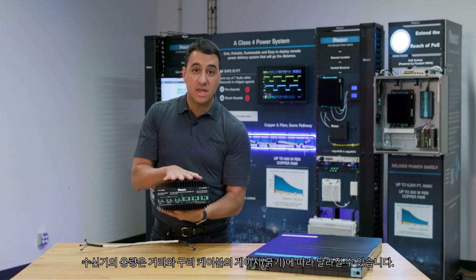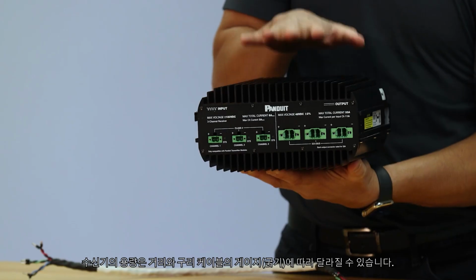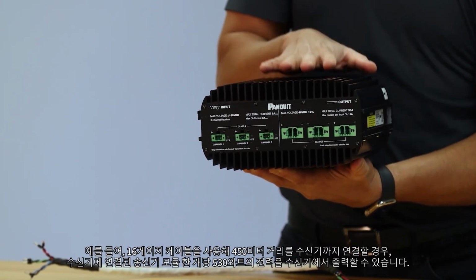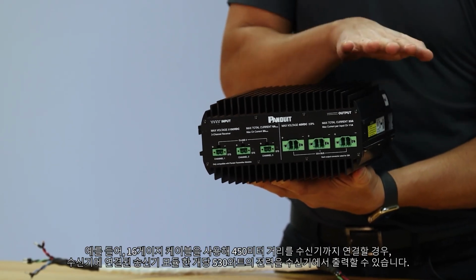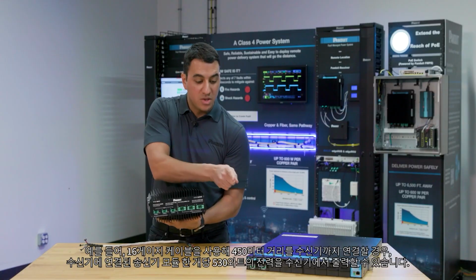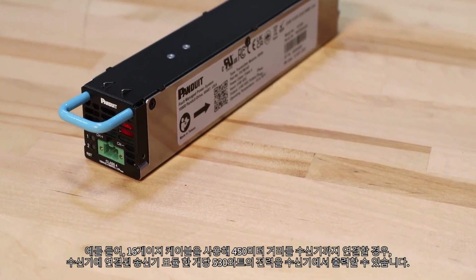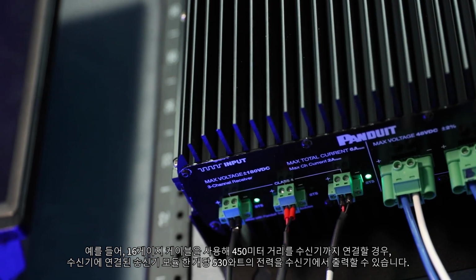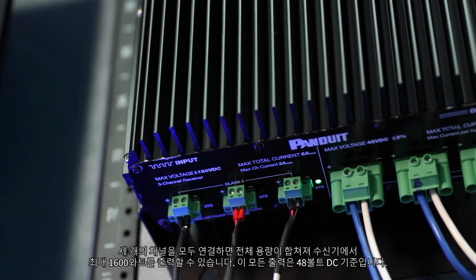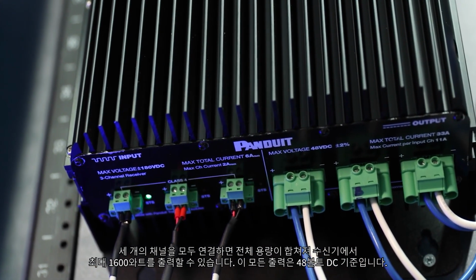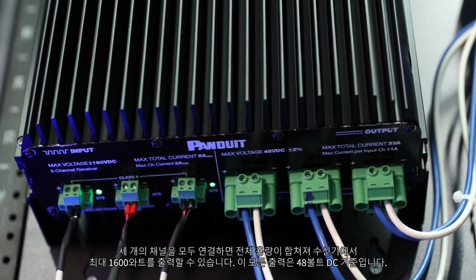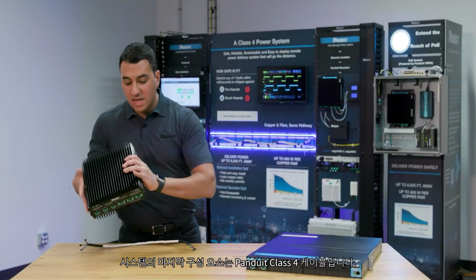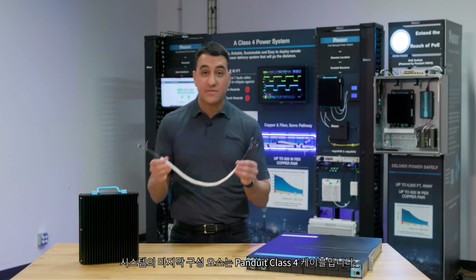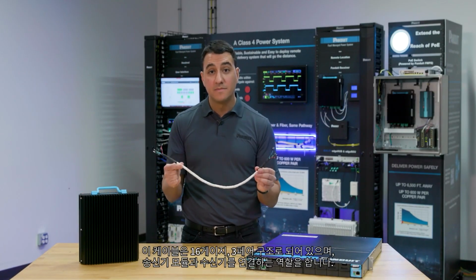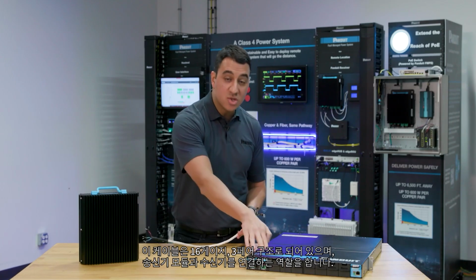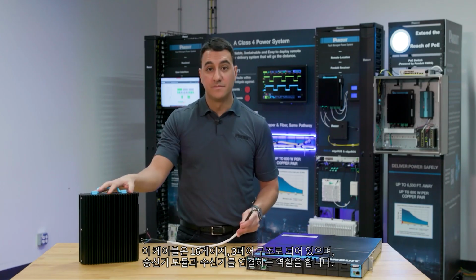Distance and the size of the gauge of the copper cable matters in terms of the capacity of the receiver. So let's say if you're using 16 gauge, running at 450 meters to this receiver, for every transmitter module connected to the receiver, you get 530 watts out of the receiver. If you connect all 3 channels, that aggregates to the full capacity, which is 1600 watts out of the receiver. That's at 48 volt DC. The last piece of the system is the Panduit Class 4 cable. It's a 16 gauge 3-pair cable, which basically connects from the transmitter module to the receiver.